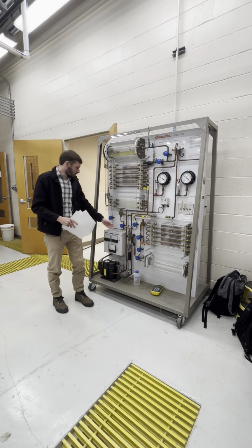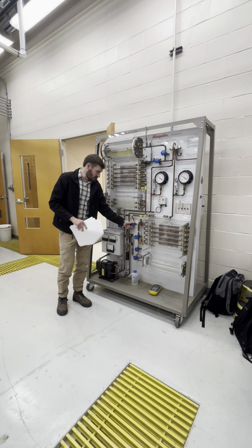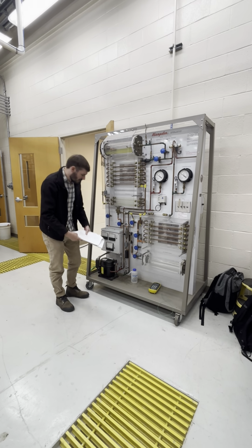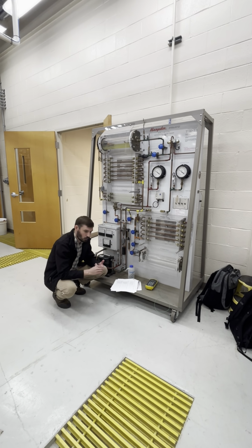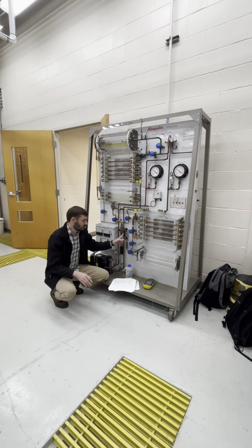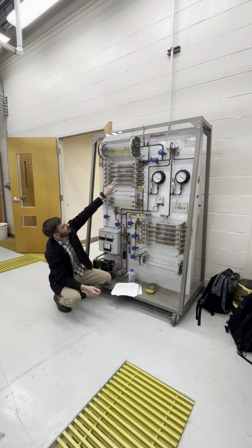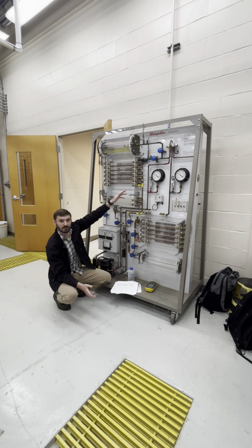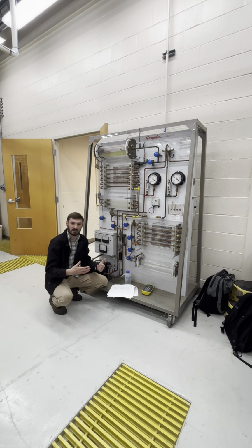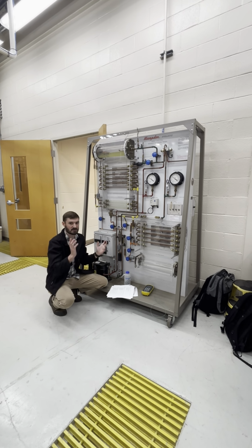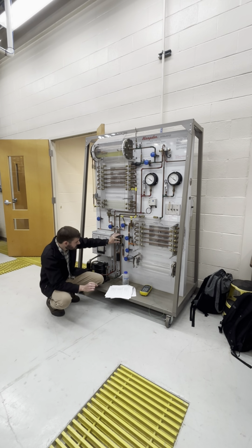For the second part, we're going to close this, okay? You're going to put your fan back on, and we're going to start using the hand expansion valve. What we're going to do is try to operate this in the 3 different regimes. You have your normal, which is going to be around 40 to 45. You're going to have a starved condition, and then you have a flooding condition. That just means that the temperature coming out of the evaporator is going to be too hot or too cold, basically. Okay? But we're going to see how that influences the rest of the system. And you're going to go through the same process. Once it gets to steady state, you take all the same measurements. Okay? This is hard. It's hard to set it.